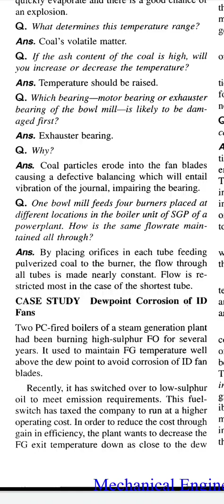Question: one bowl mill feeds four burners placed at different locations in the boiler unit of a power plant. How is the same flow rate maintained all through? Answer: by placing orifices in each tube feeding pulverized coal to the burner. The flow through all tubes is made nearly constant. Flow is restricted most in the case of the shortest tube.